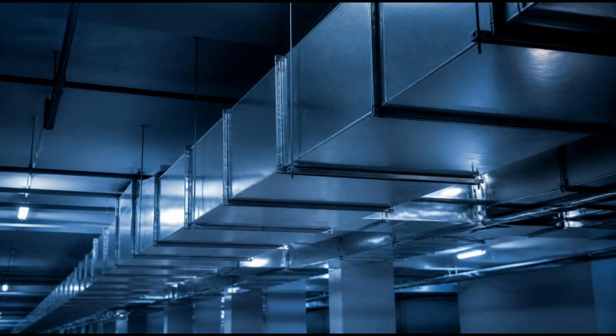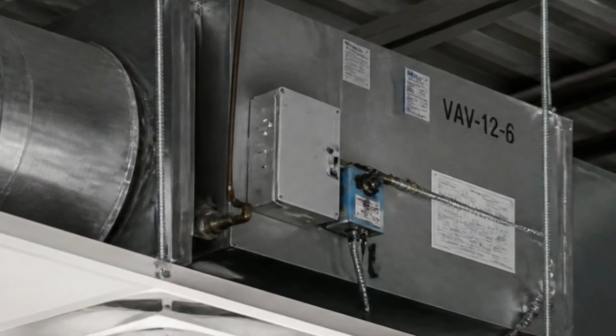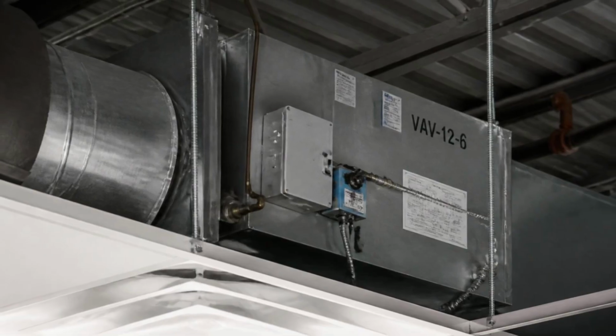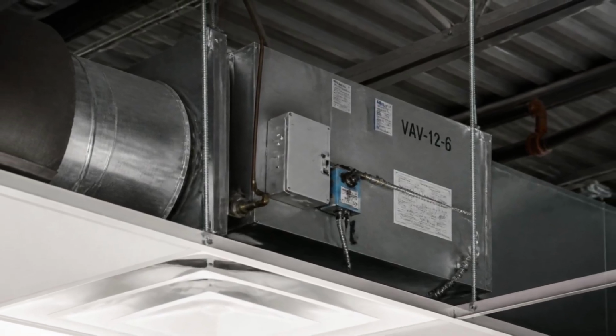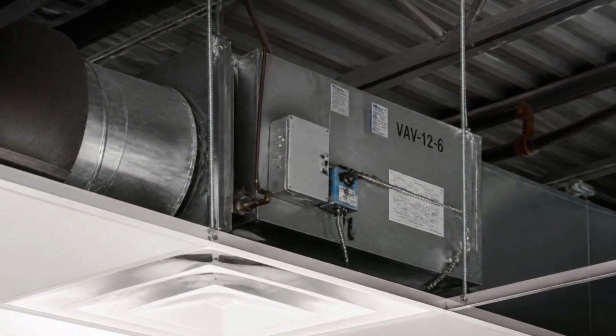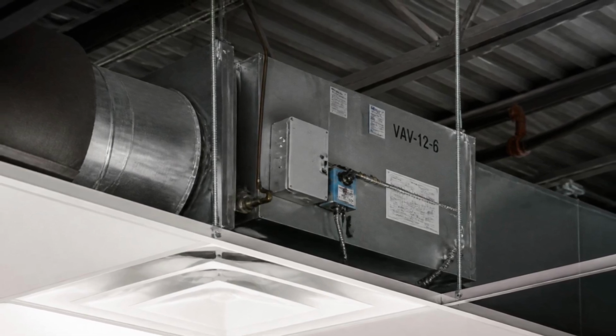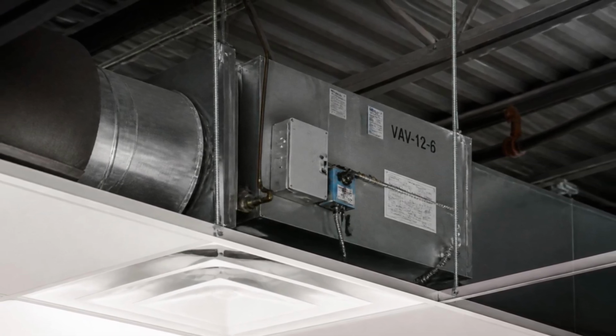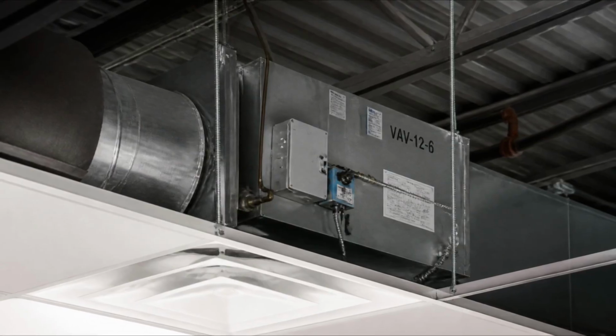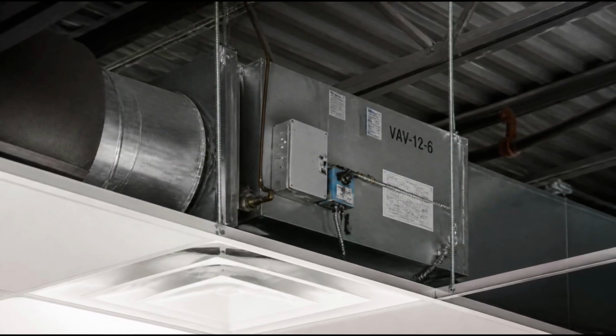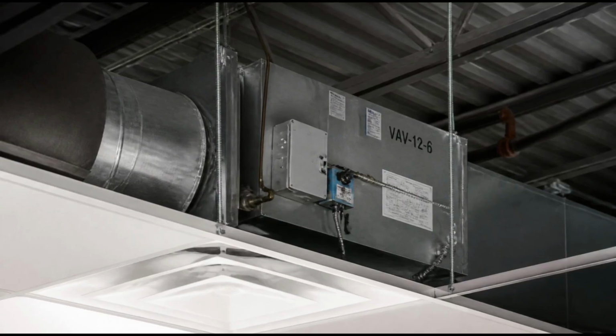This balance between recirculation and fresh air intake is one of the fundamental design choices in commercial ventilation. Too much recirculation and indoor air quality can suffer. Stale air accumulates. Carbon dioxide levels rise as occupants breathe. Odors and humidity may build up without adequate dilution. But too much fresh, outside air means the system must work harder to condition it, since outdoor air arrives at whatever temperature the weather provides and must be brought to the proper indoor conditions before it can be useful.